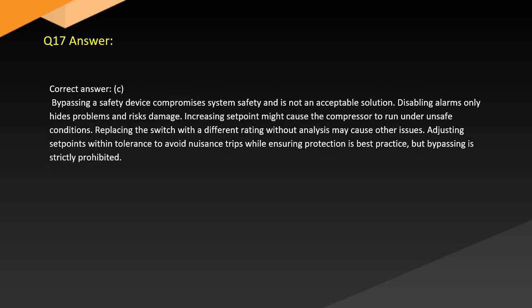Answer. Correct answer: C. Bypassing a safety device compromises system safety and is not an acceptable solution. Disabling alarms only hides problems and risks damage. Increasing set point might cause the compressor to run under unsafe conditions. Replacing the switch with a different rating without analysis may cause other issues. Adjusting set points within tolerance to avoid nuisance trips while ensuring protection is best practice, but bypassing is prohibited.